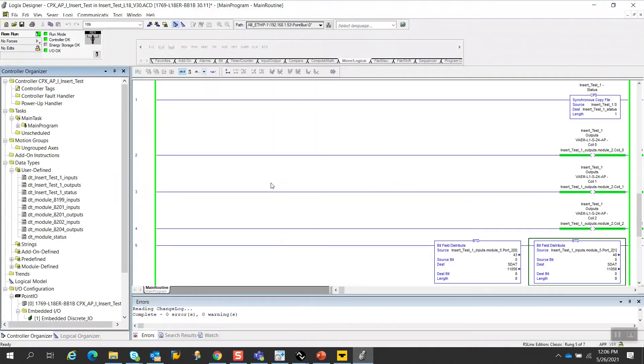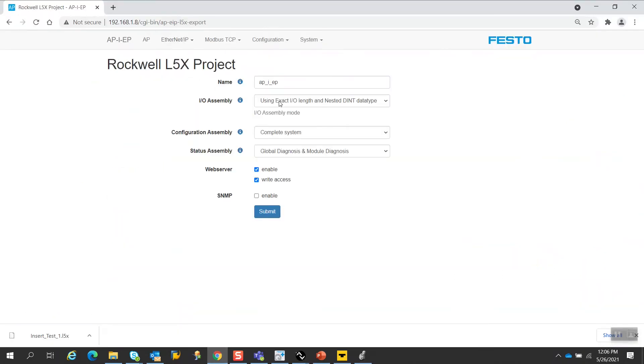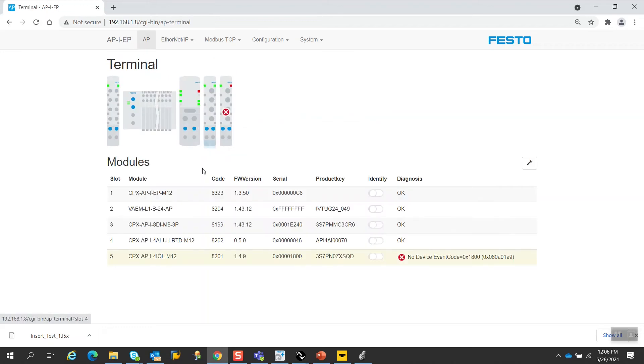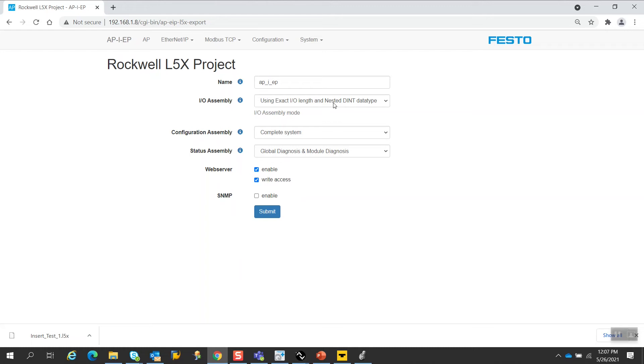This manifold right now is running in the Logix software, so I have this configuration set up with a very simple program. This was set up by using the L5X export function using nested data types, using the default settings of the latest firmware, which is firmware version 1.3.50 of the Ethernet IP adapter. The idea here is to use the nested data types, and after inserting a module with very simple editing to perform on the data type, this will allow one to insert a module into the system and make some very simple changes to avoid changing the tag names for all of the modules that physically would get shifted in the AP-I system.